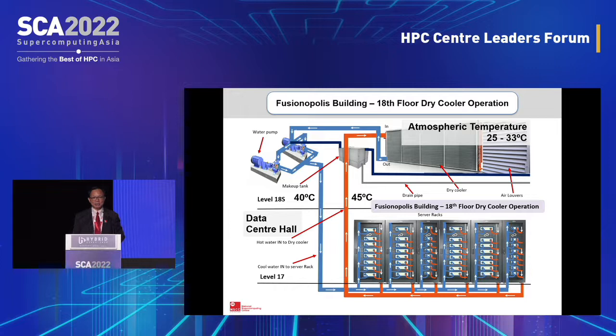In the next part, I'll talk about how we made use of being on the upper floor, level 17, to use dry coolers, meaning the evaporative loss is actually 0. This is a closed loop, and in Singapore we have limitations on using fresh water, so evaporative cooling isn't a great idea due to the high cost of fresh water. By using a closed loop dry cooler system, we were able to expel heat at the level 18 floor, which has pretty high winds.